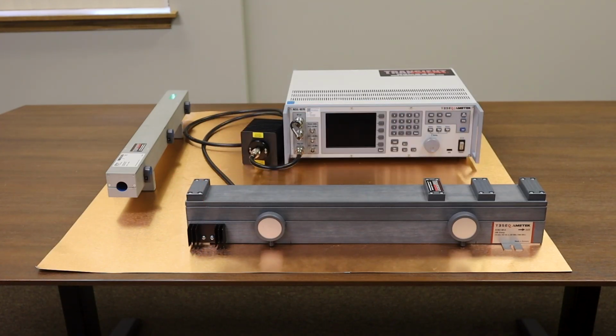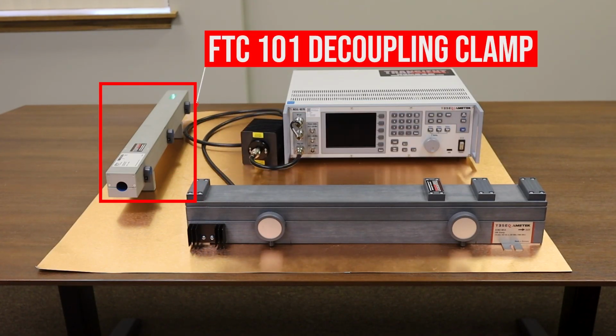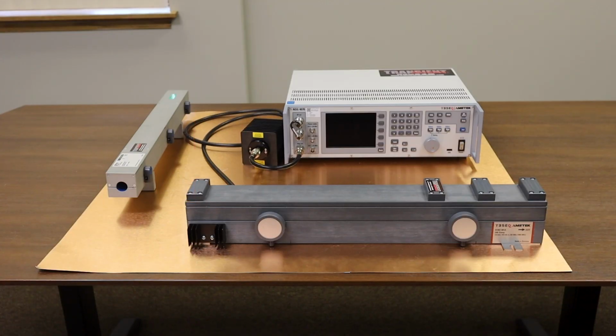You will also notice on the side we have the FTC 101 decoupling clamp. This can be placed in the setup to help isolate the auxiliary equipment. Now we can go ahead and run the test, and it will apply the calibrated stress levels to the cabling going towards the equipment under test.